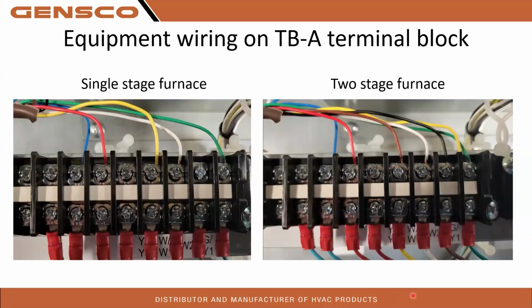Equipment wiring. This is the TBA terminal block, the ones in the pictures on the left-hand side there. These are examples of what it's going to look like if you have a two-stage and single-stage furnace. For single stage, you can see we have our green wire into our G, white into W1, yellow into Y, red and common. When you come over to the two stage, you can see in this picture I have yellow and green both tied into that G. My black is now on W2 and my brown is now on my Y2. So first stage cooling, second stage cooling.